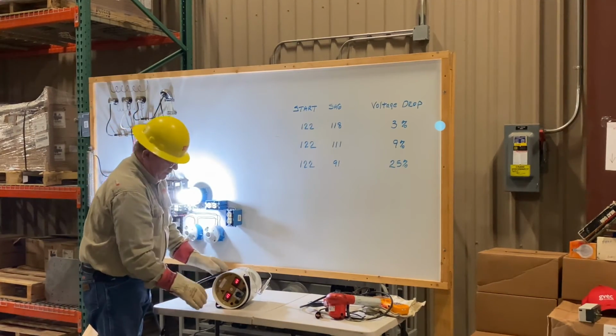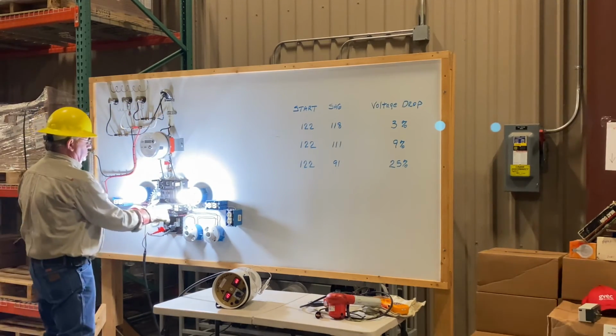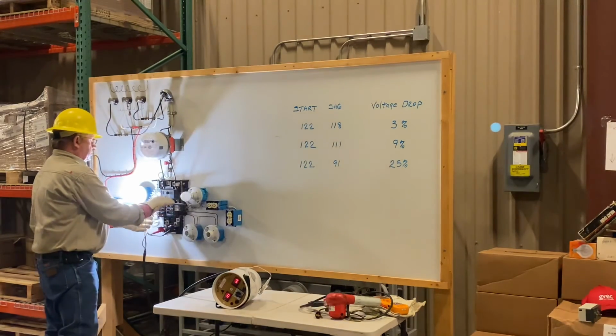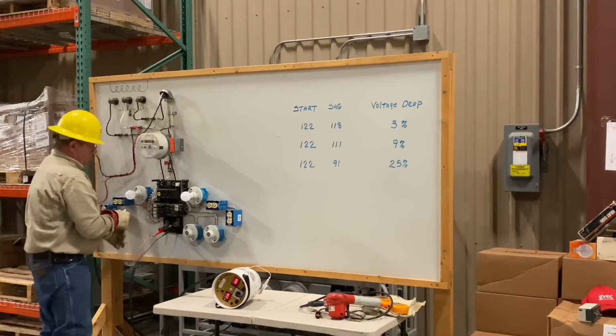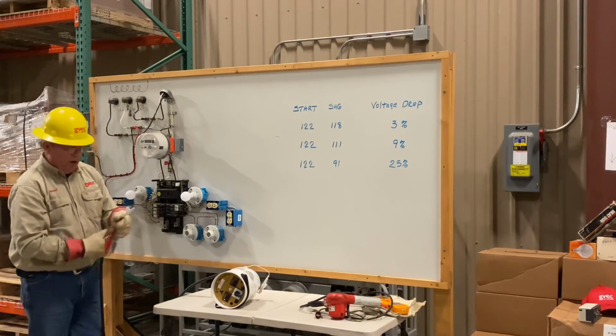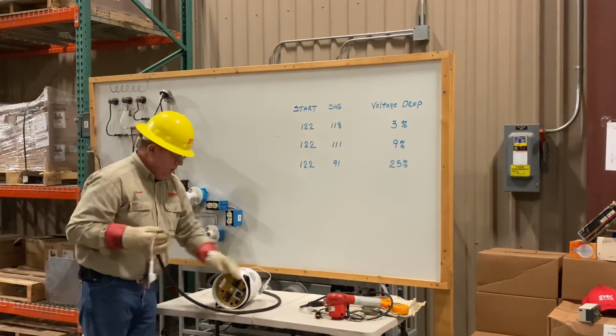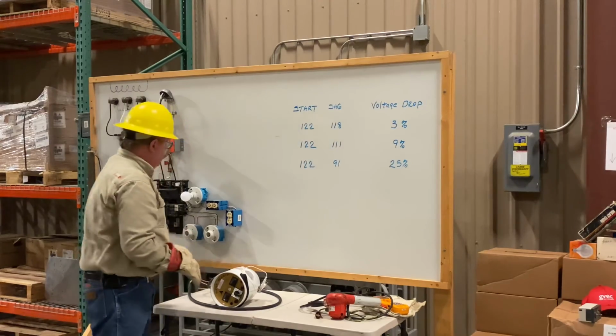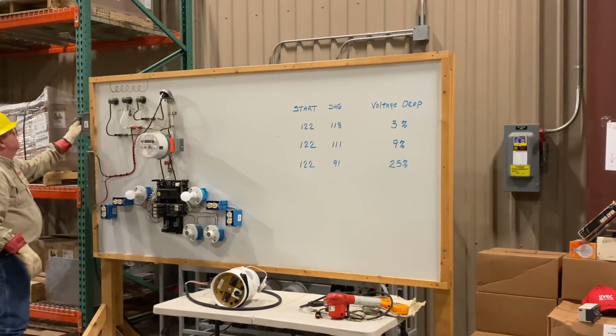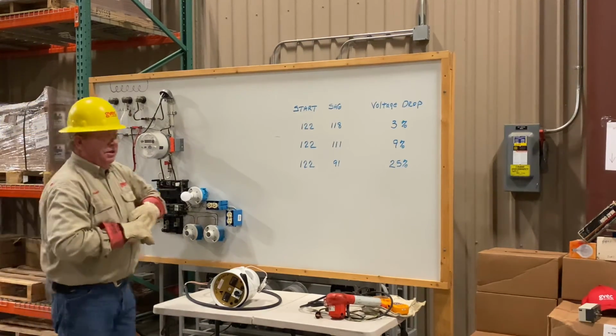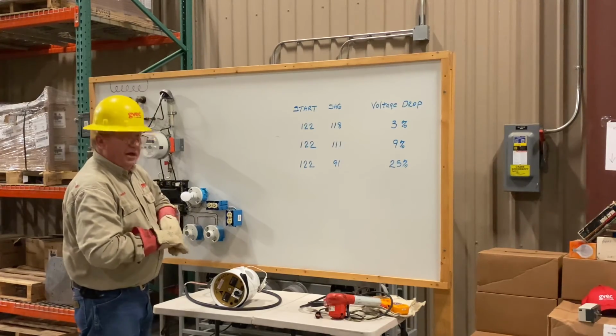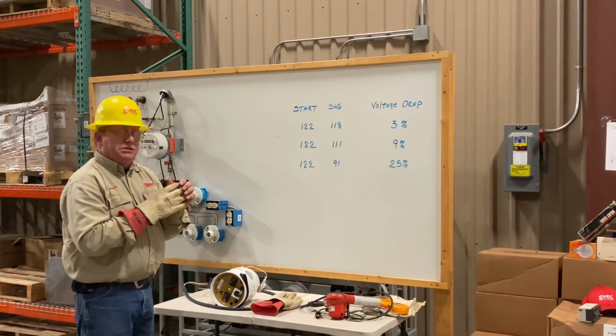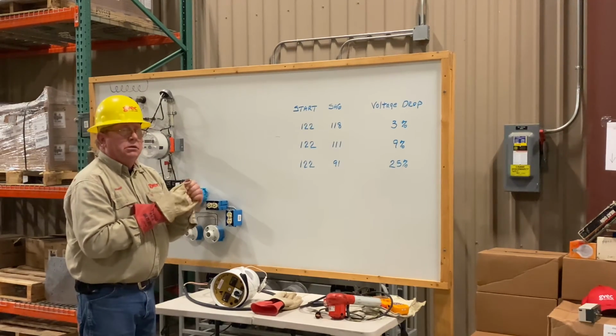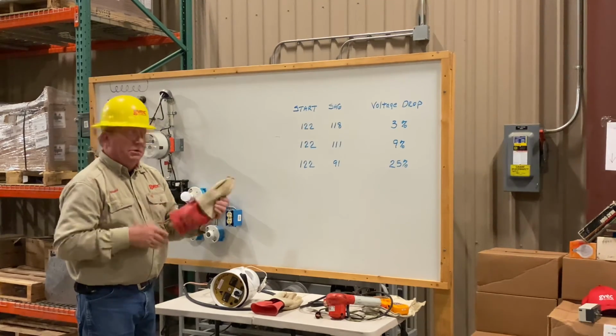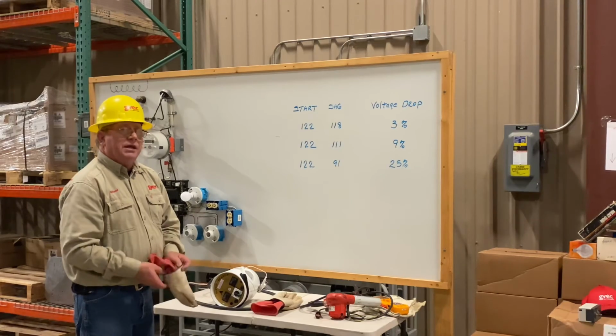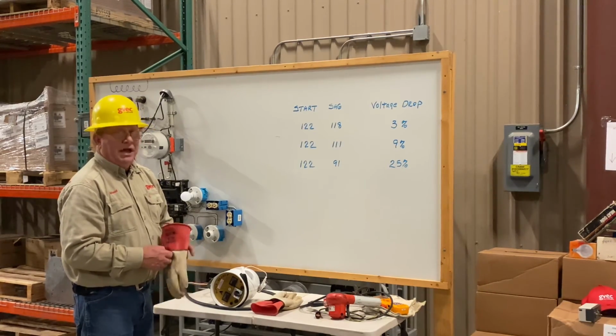Now we found that sometimes we have to let it run for a little while. I like to tell the story that we were working a voltage complaint in Nixon. I had an external load. I'm going to turn this power off. We had an external load. We were in the meter socket running 10, 11 amps. It took 15 minutes before the voltage changed, before the connector deteriorated to the point that we could see it with a voltmeter. Now, thermal imaging, infrared, we saw that connector long before it failed, in contrast to the hot connectors.